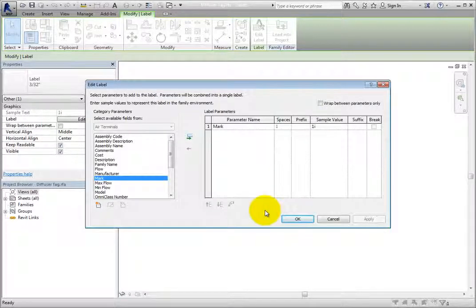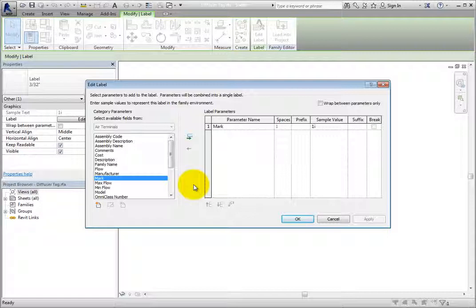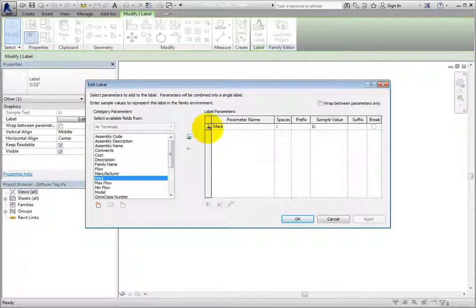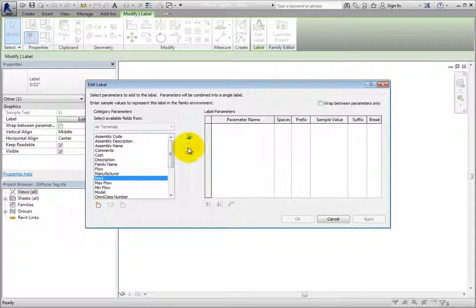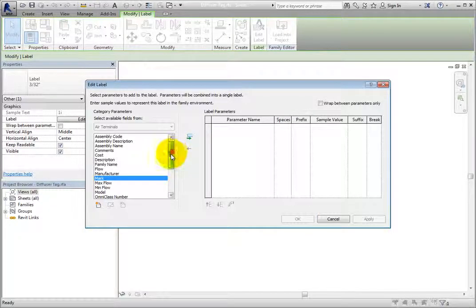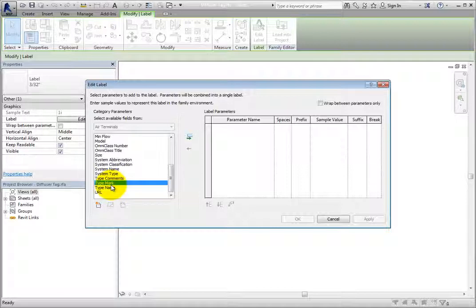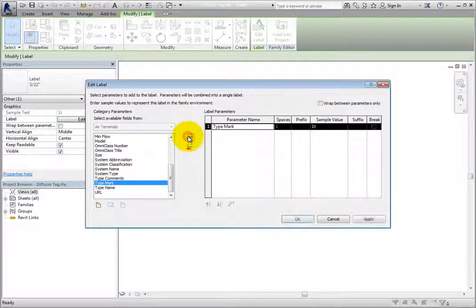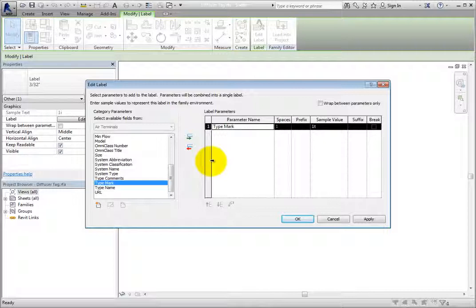Since air terminals are typically referenced by their type and not every single instance in the project, I'll highlight the row in the Label Parameters section and choose Remove Parameter from Label. Then I'll select Type Mark in the Category Parameters list and choose Add Parameter to Label. Now when this tag is loaded into the project, the label will reference the type mark of the element.